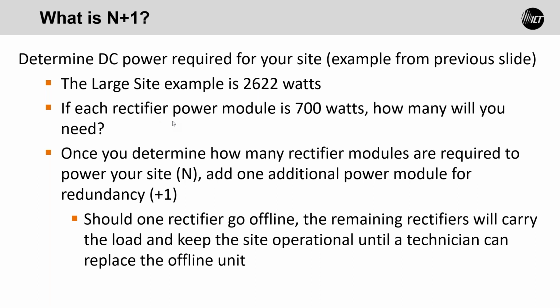So in this case you would need 4 power modules for your N, and the 5th would be your +1. Once you determine how many rectifiers are required, the redundancy is that +1 rectifier. Should one of the rectifiers go offline for whatever reason, you'd get an alarm notice by email letting you know that one of the rectifiers has gone offline.